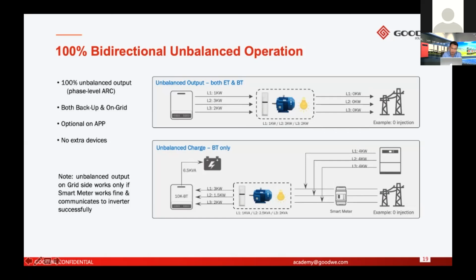Okay, so it means it can output, for example, on phase 1, there's no load. So on phase 1, they do not output power. The output power on phase 1 is 0 kilowatts. But on phase 2, they have 3 kilowatts of loads. So on phase 2, they can output 3 kilowatts of power.